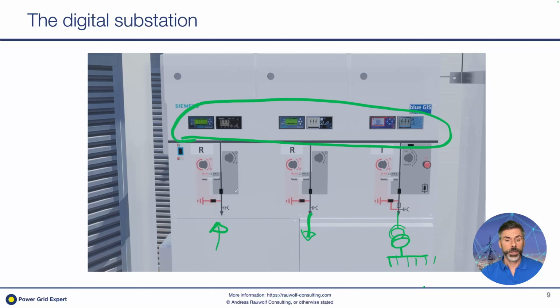And those are measurement devices. They can deliver measurement values from the medium voltage side, like voltages, currents, power, cosinus phi, and so on. And they also deliver, well, let's say their main task is the fault detection, short circuit, earth fault, and so on, and the alarm towards the SCADA system, helping during a fault situation the people who are looking for the fault location to find it quickly. The sensors for voltage and current: the current sensors are normally here around the cable of the medium voltage or around the bushing. We will also have a closer look in a follow-up video here.